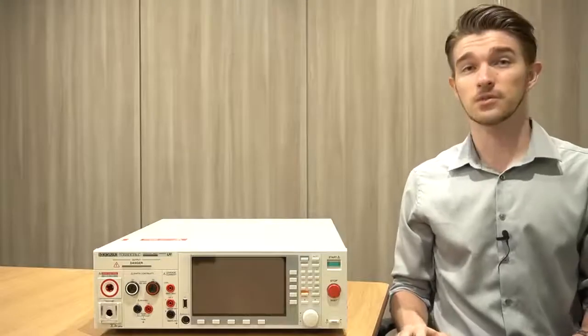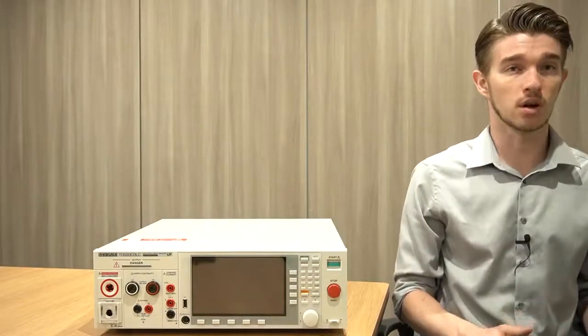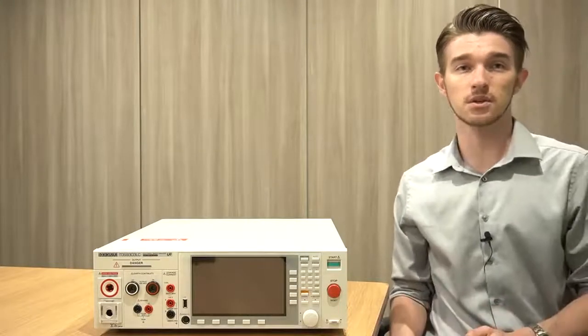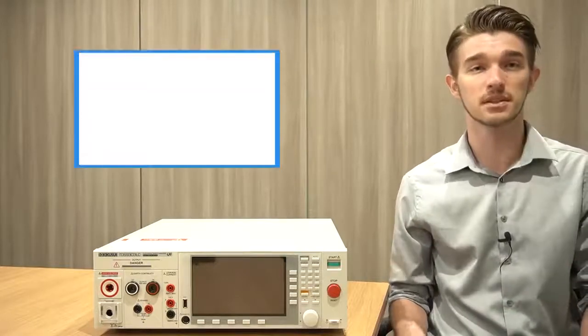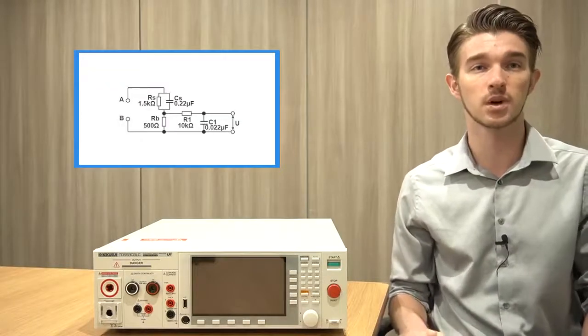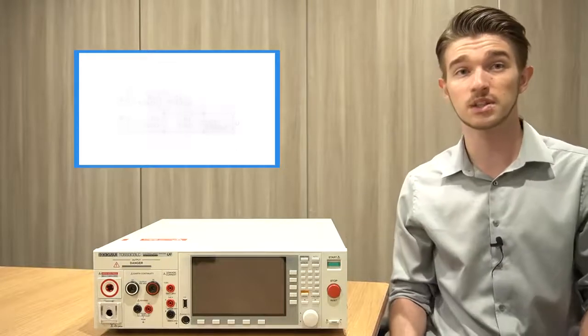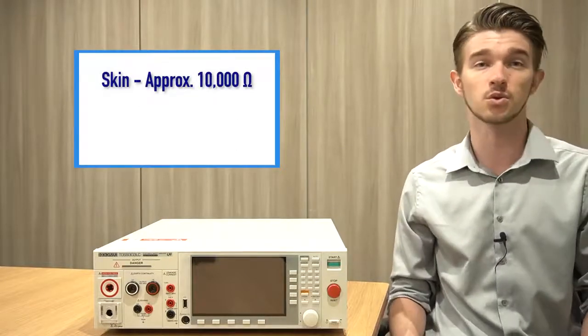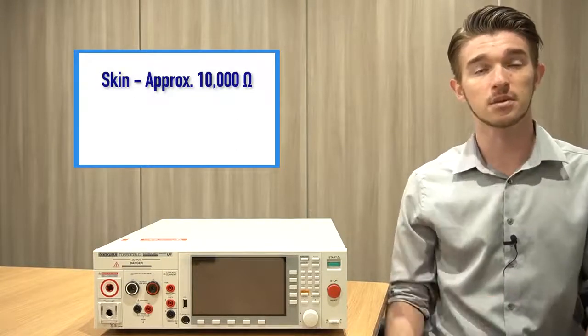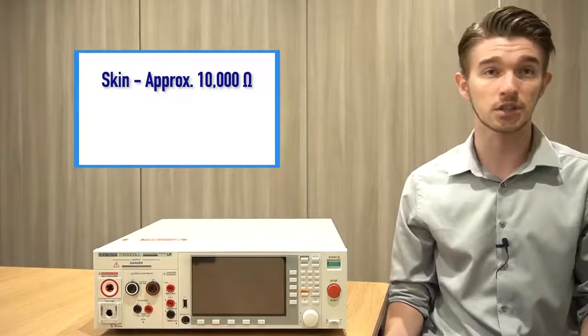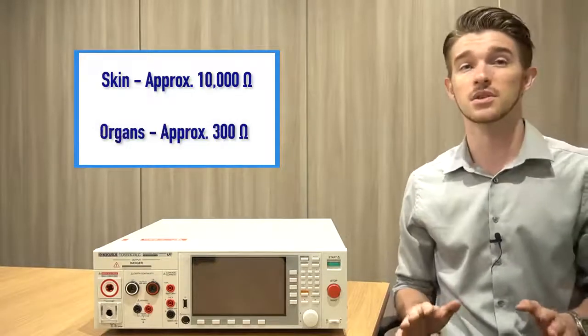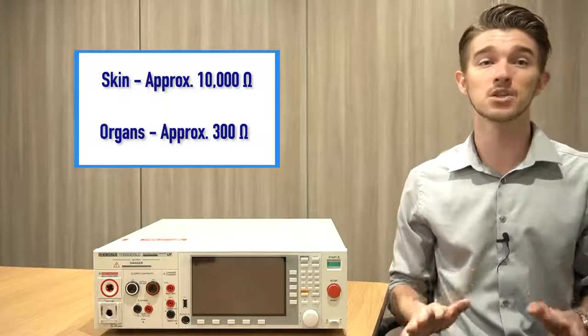These standards are sufficient when applied to regular electronics, but measurements for these standards are conducted using human impedance networks simulating how electricity reacts with human skin, which exhibits a relatively high electrical resistance.